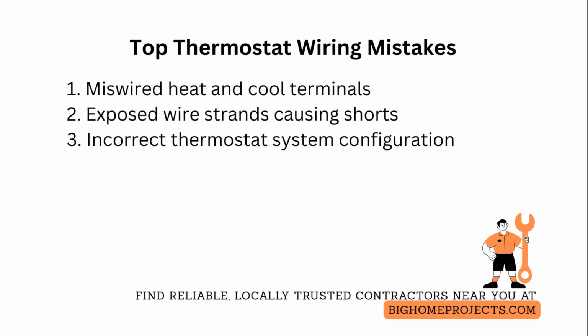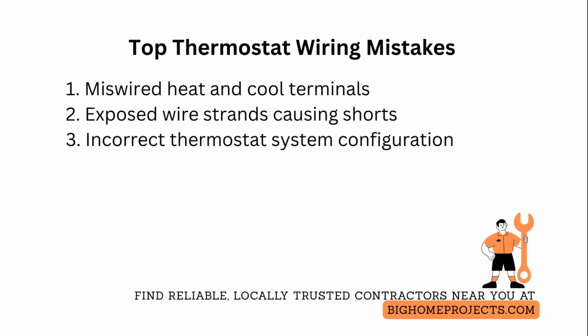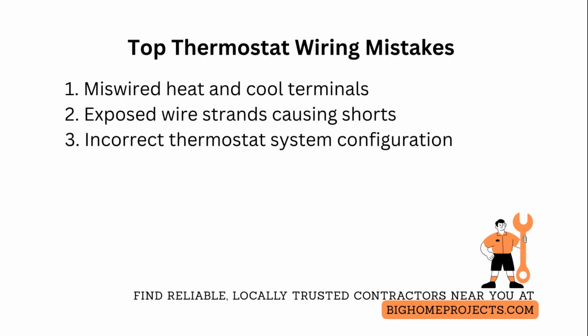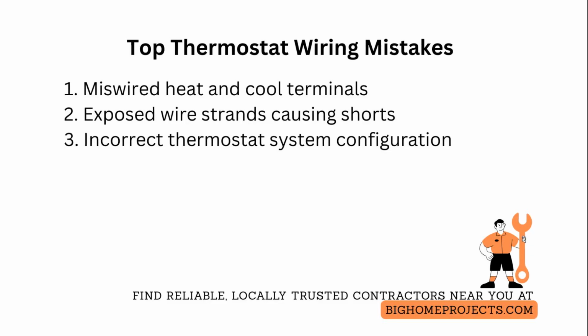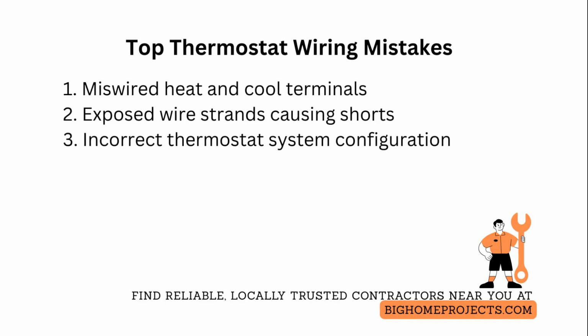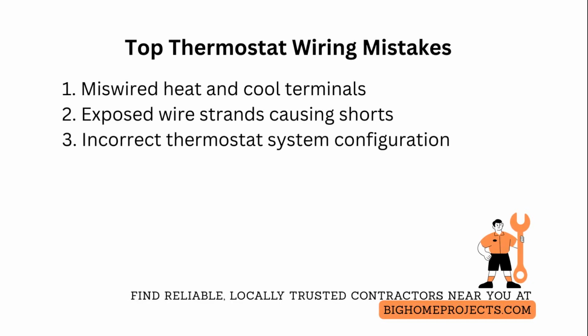One of the frequent problems is failing to configure the thermostat for the correct system type, resulting in simultaneous calls or disabled stages. Correct this by reviewing the installer setup menu, setting the system type to single-stage heat, heat pump, or multi-stage as appropriate, and verifying on the control board that only the intended relay is energized.